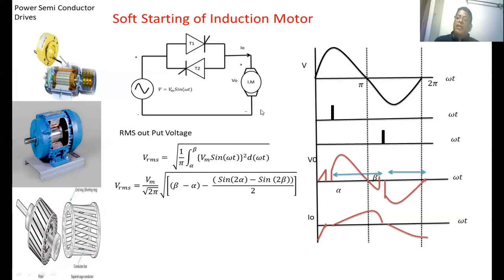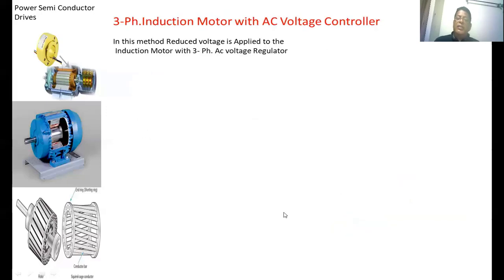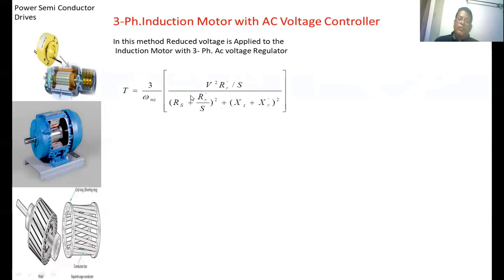Sometimes this circuit is also used to control the speed of an induction motor. If the rating of the induction motor is very high, use two anti-parallel SCRs. For lower ratings, a TRIAC is used between the source and the load circuit. For three phase induction motor with AC voltage control, we apply the reduced voltage by means of a three phase AC voltage regulator. The torque developed in a three phase induction motor is equal to 3 by omega_s times V squared times R_r' by S, divided by (R_s plus R_r'/S) squared plus (X_s plus X_r') squared. If the slip is high, the torque is directly proportional to V squared, where V is the applied voltage. If you decrease the voltage, the torque decreases and the speed of the induction motor also decreases.